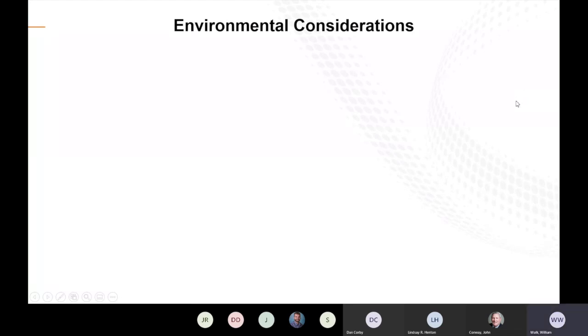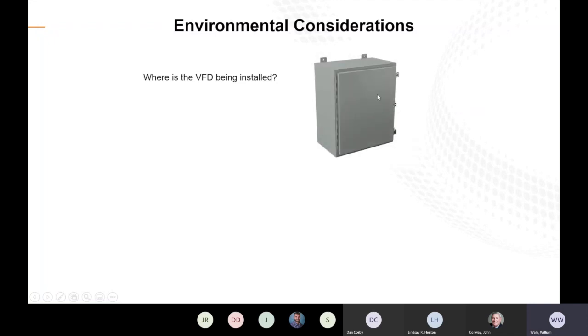Next thing to consider whenever you're installing VFDs is your environmental considerations. A couple of questions to ask for yourself. Where's the VFD being installed? Is this going to be a panel mounted VFD? Is it going to be installed on the wall? What am I going to need for that? So what is the atmosphere like that this VFD will be installed in? Is it a caustic, acidic environment? Do we have a lot of dust? Is it in an electrical room isolated from everything else, which would be the most ideal?